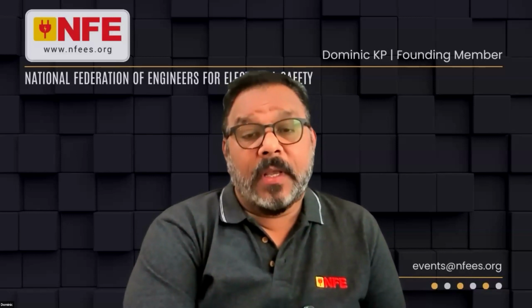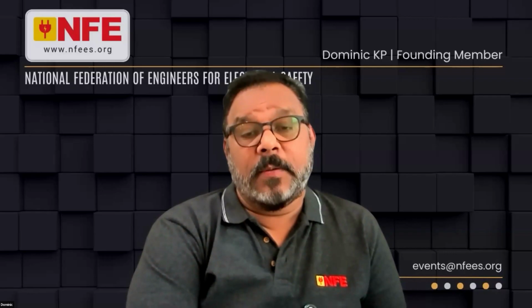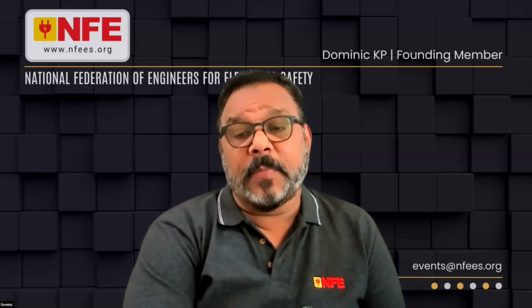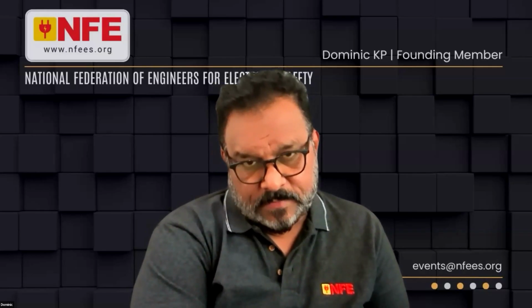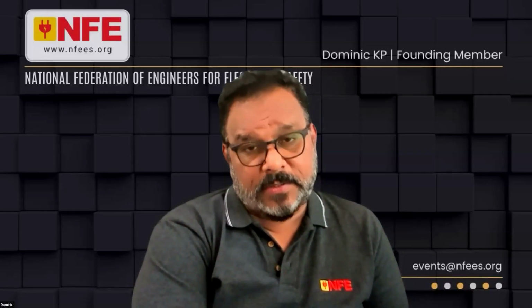While they unmute, Gopal Singh Yadav asks, what is the importance of earthing during termination and after termination? Earthing is very important, because when we fold back the armoring, we have to connect that armor to the earth bed and do the earthing properly. If we do not do the earthing properly, whatever surface leakage currents and circulating currents are there will not be grounded, and it will affect the performance of the termination. So it's very important to do the earthing.